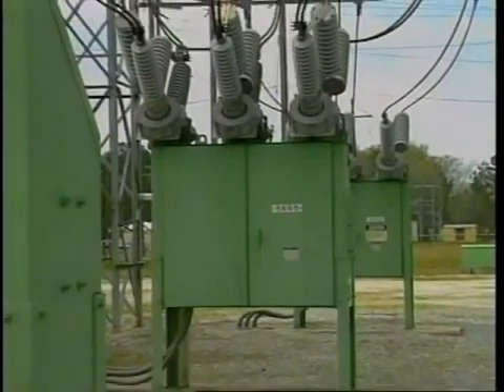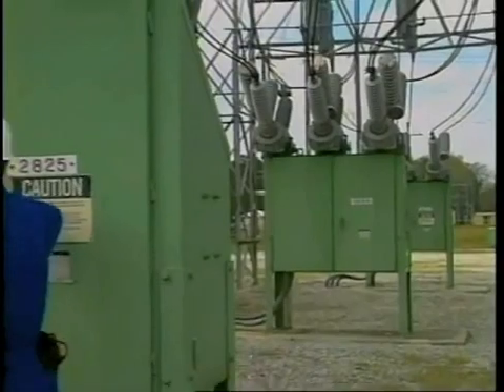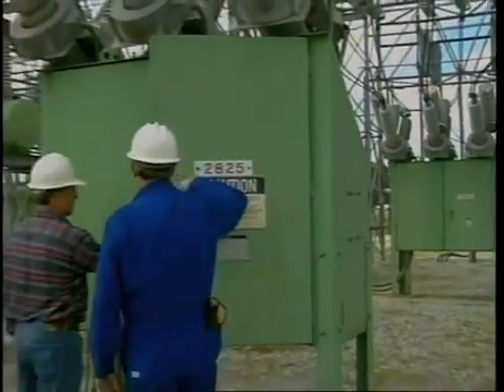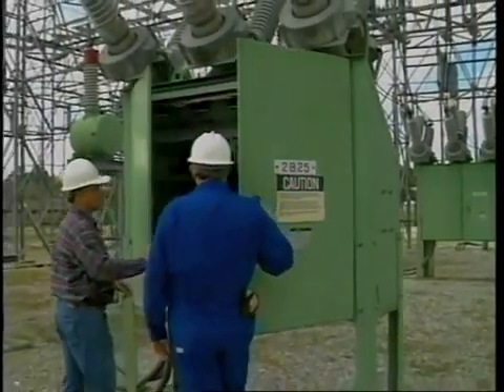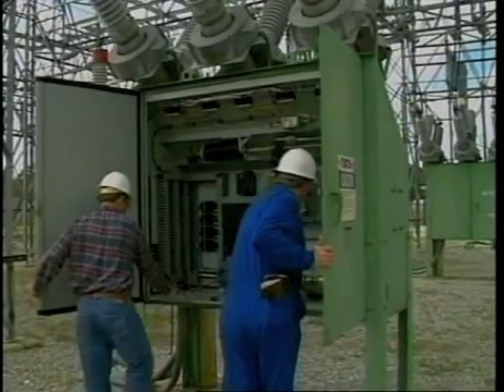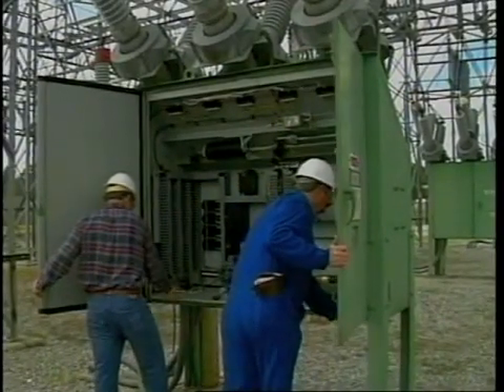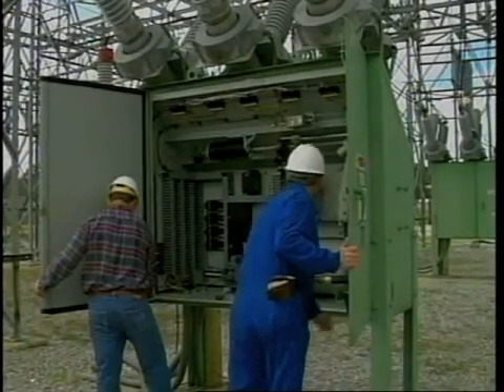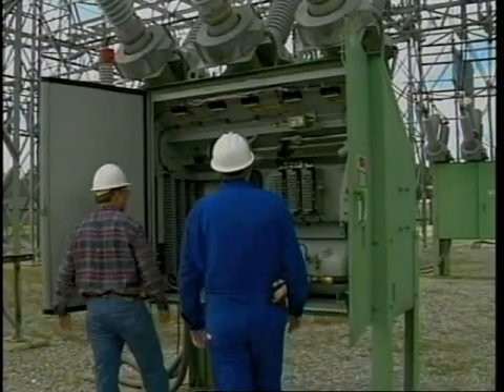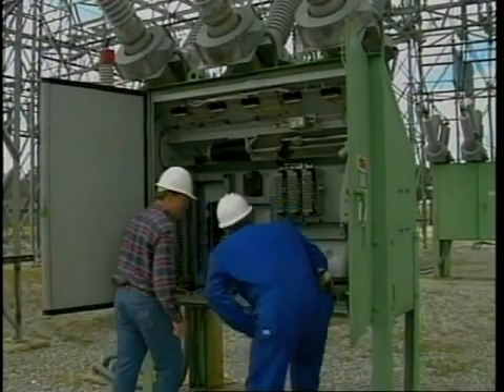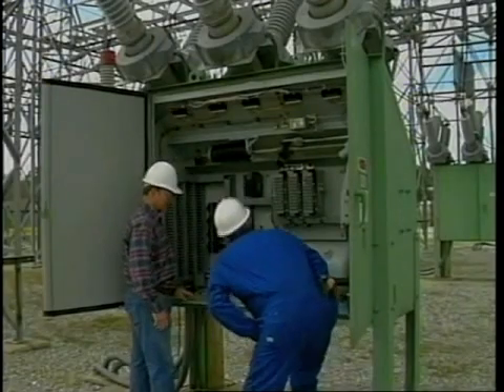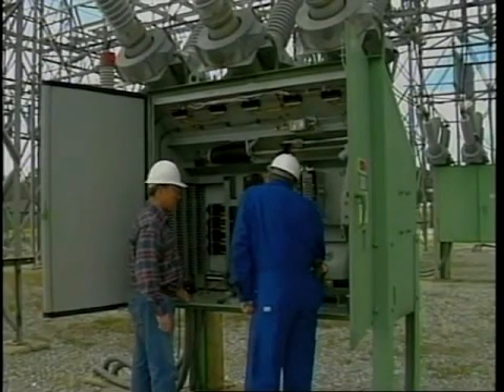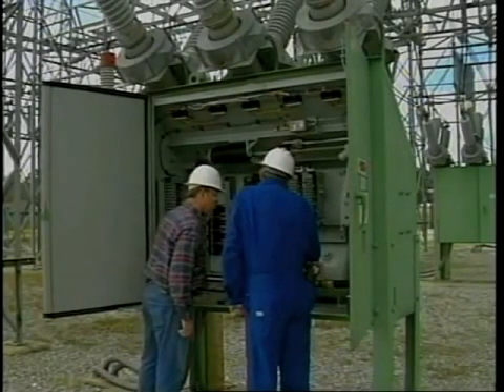Sulfur hexafluoride circuit breakers provide an excellent insulating medium for arc interruption. Sulfur hexafluoride gas has a dielectric strength that is 2.5 times greater than that of air. In this program, we'll look at the major components that make up sulfur hexafluoride type circuit breakers, as well as pointing out generally accepted safe work practices for this type of equipment.